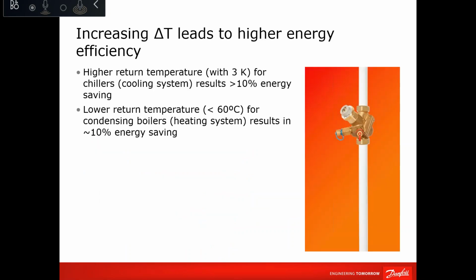So 3 degrees on the return temperature is direct more than 10% total cooling energy saving, which means 10% on one chiller, which will have like 150 kilowatt, is equivalent to the total energy required of the pumps combined, which means having 10% on chillers is equivalent to 100% on the pump.